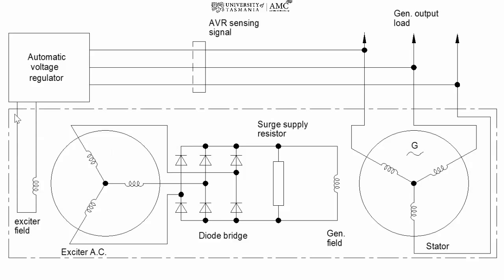Now the exciter has its stationary field coils, and from there we induce an EMF into our rotor windings, our conductors, and from there we get an output. We put it through a set of diodes, which are basically one-way valves. It only allows the flow in one direction, and from that we take our DC. From here we supply the field coils for the alternator in DC.